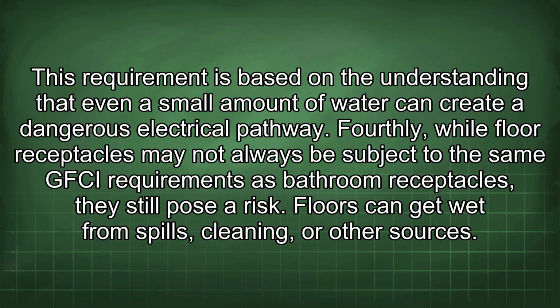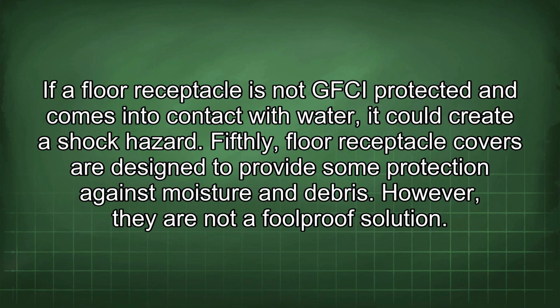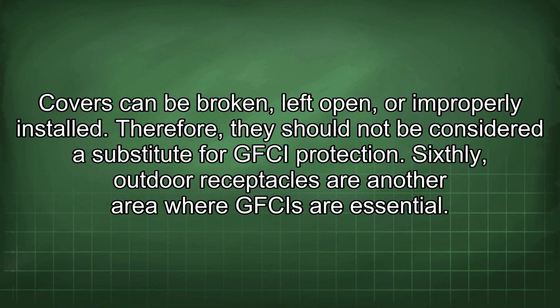Fourthly, while floor receptacles may not always be subject to the same GFCI requirements as bathroom receptacles, they still pose a risk. Floors can get wet from spills, cleaning, or other sources. If a floor receptacle is not GFCI protected and comes into contact with water, it could create a shock hazard. Fifthly, floor receptacle covers are designed to provide some protection against moisture and debris. However, they are not a foolproof solution. Covers can be broken, left open, or improperly installed. Therefore, they should not be considered a substitute for GFCI protection.